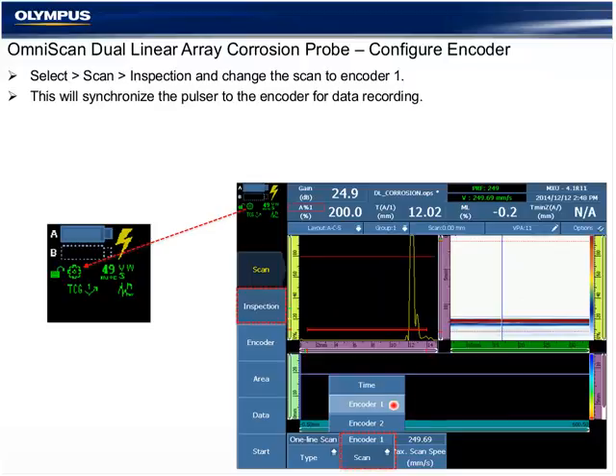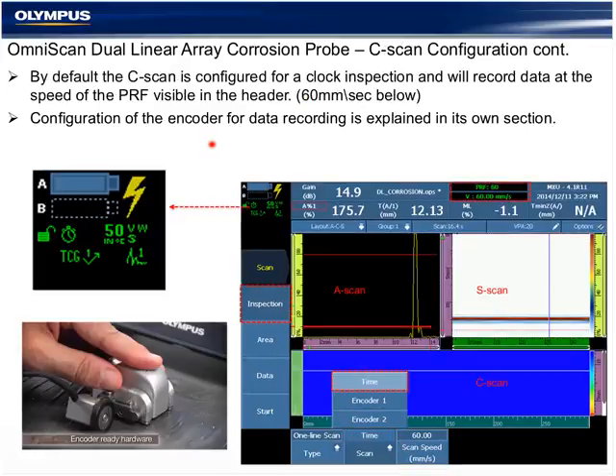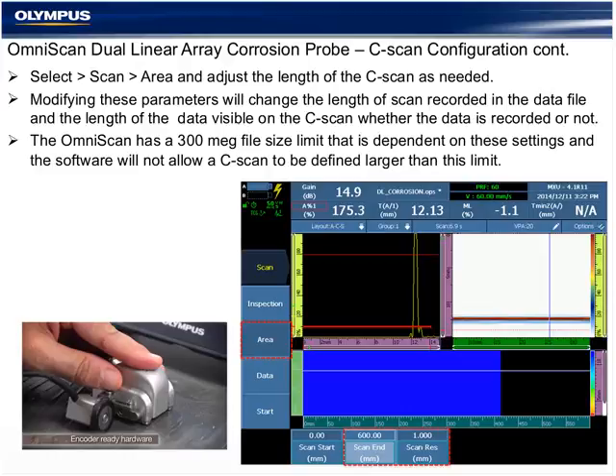Selection of encoder 1 here is going to change the time icon to a little mechanical wheel icon, telling the operator that this is configured for recording all of the A-scans using a scanner or a wheel encoder. And we can see here that the typical mini wheel ports are built directly into the stabilization system around the probe. When a C-scan is selected, we'll also enter the start, end, and scan resolution. This will affect, on a clock inspection, how fast the C-scan builds left to right and how much data is buffered should you select pause and save data.